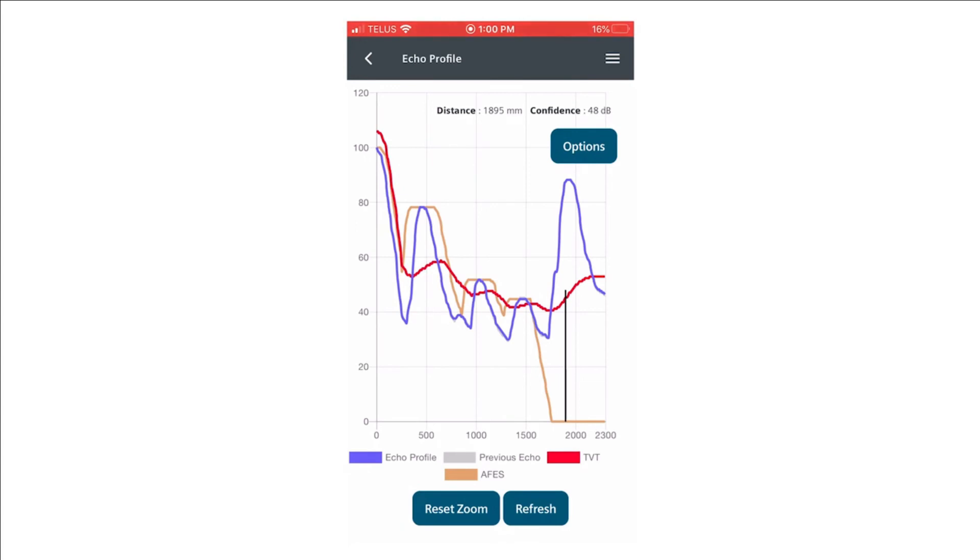So you can see clearly the brown auto-false echo suppression curve has now been drawn around the false echoes, and those three echoes will never be selected in the future.